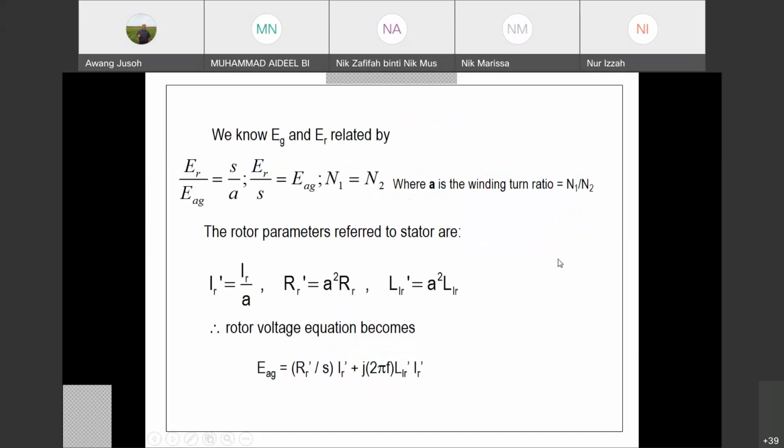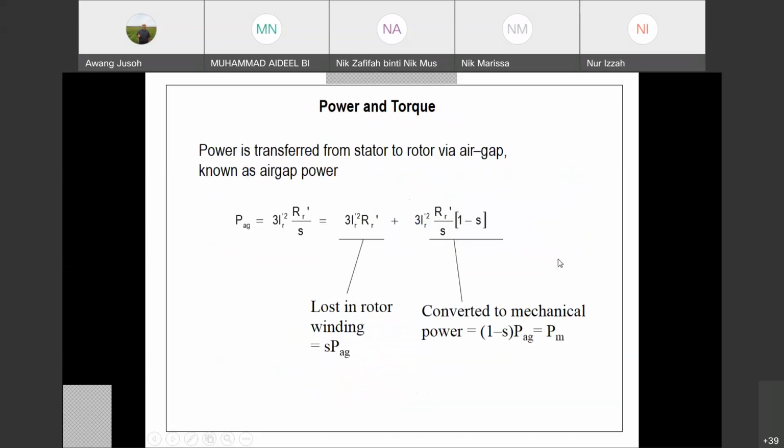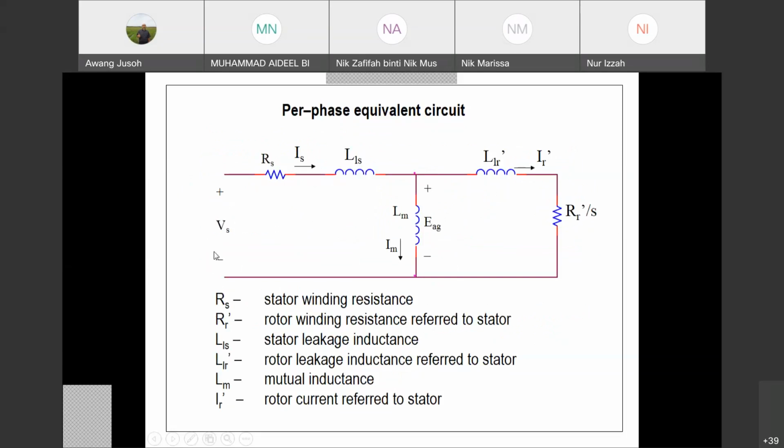We go back to here. So now the power coming to here. When we supply voltage to the motor, the power comes to here. P in, power input. So power input equals, everybody knows the formula, root 3 V line I line cos theta. That gives you the power input. So you supply power to the motor, coming to here, and then you see the resistance there. That means it represents losses in the stator winding. So P in minus losses in the stator winding, you get P here.